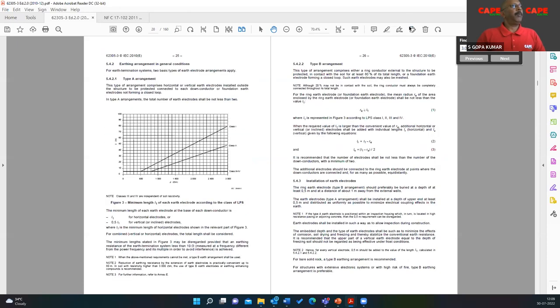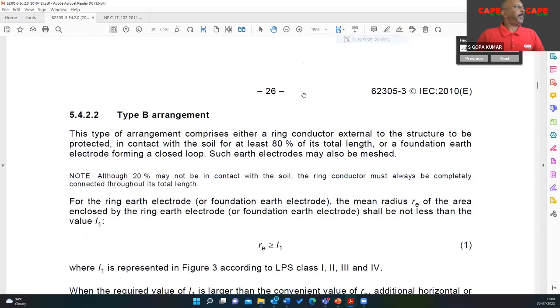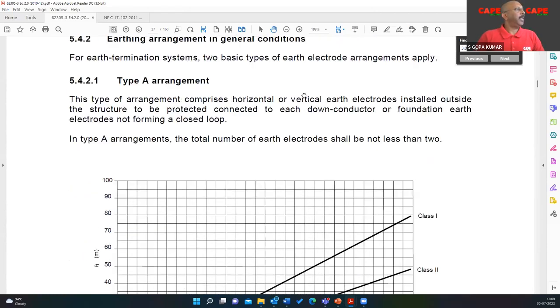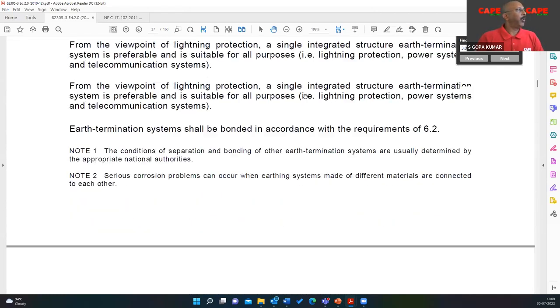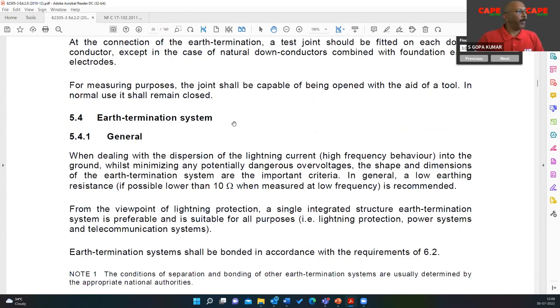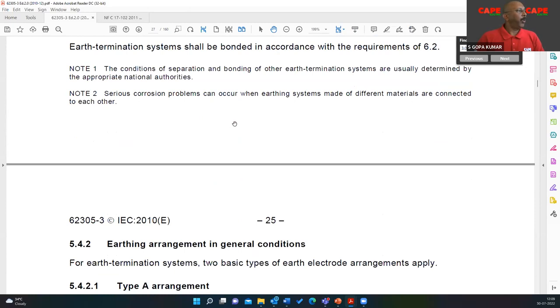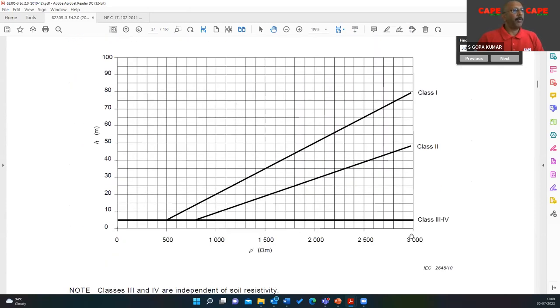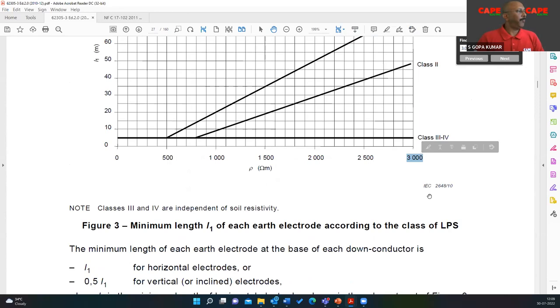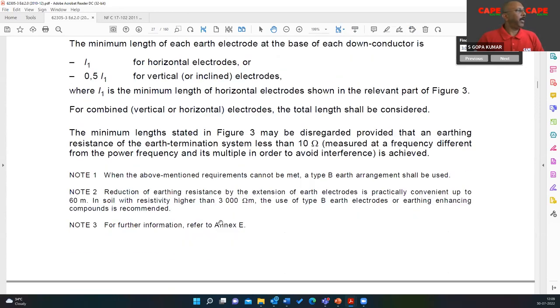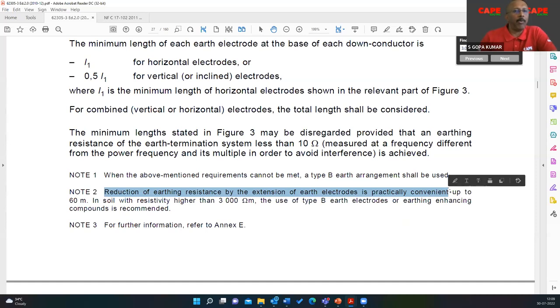So here is the table. You can find this particular picture in the standard. Here you can see the section is 5.4.2 or 5.4, earth termination, how to make earth termination. Now you look at the particular picture; up to 3000 ohm meter is shown. Now you read the note here. Reduction of earthing resistance by extension of earth electrode: several techniques are there. One technique is extending the earthing conductor in the soil, practically convenient up to 60 meter.